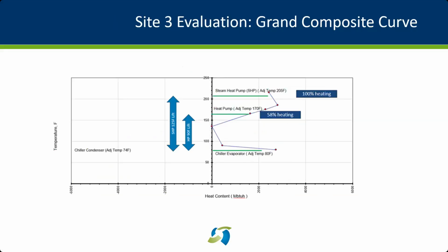Now, if we take the same diagram and convert it to a grand composite curve, you can see, for instance, that we can pick up heat from a chiller evaporator at 80 degrees at the bottom, move it up by a 90-degree lift with a heat pump to provide 58% heating for hot water, or move it up with a 125-degree lift to make some low-pressure steam, and that could potentially provide 100% of the heating in this case. So the grand composite curve can be used to estimate the heat pump lift and the amount of heat that can be delivered through the heat pump based on the waste heat available.